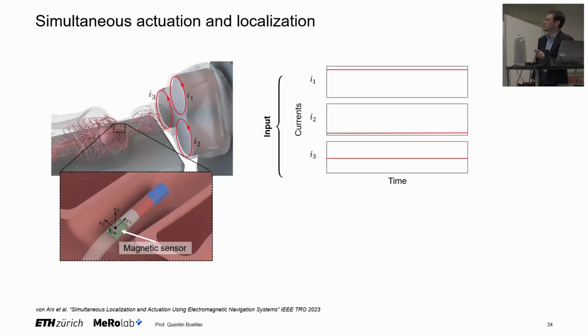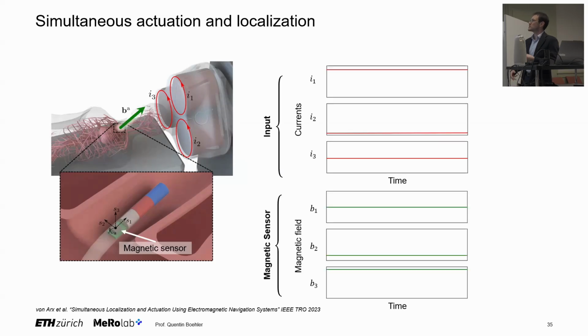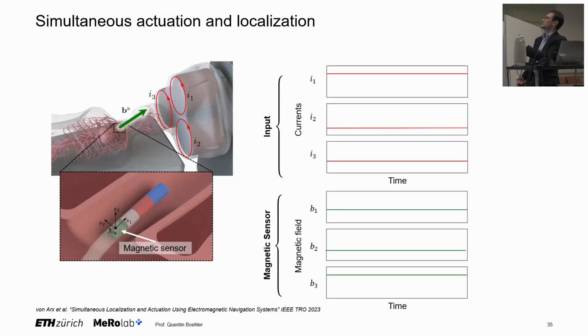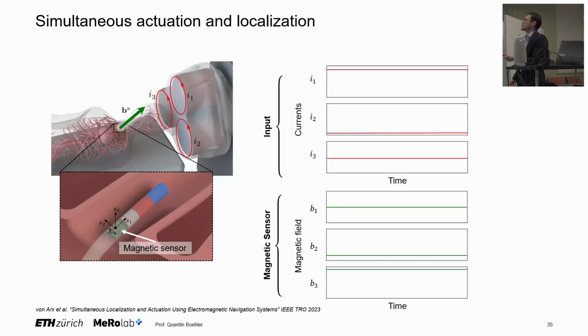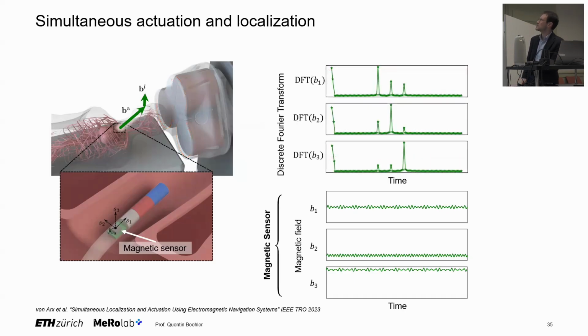And the approach we proposed was, as I mentioned, we use a magnetic field to actuate. So you would change your currents, and this current would change your magnetic field, and that's how you steer your device. On top of this so-called actuation current, we would add small oscillations, small ripples, with frequencies that are different for each of the coils. These currents would produce ripples in the magnetic field, which would be measured by this magnetic sensor. Then you apply a very standard discrete Fourier transform, so you're trying to isolate the different frequency components for your magnetic sensors.